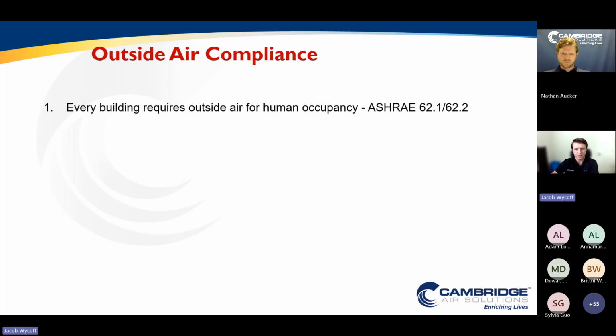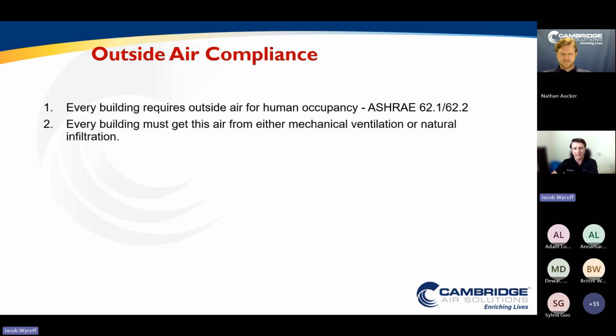So we know that every building is going to require some level of outside air for human occupancy. We know that from ASHRAE 62.1 building codes. Every building is going to have to get that air either through mechanical ventilation in most places with modern codes, or from natural infiltration. So even if the building does not require mechanical ventilation, it's going to have air infiltrating into the space somehow. And if you were to provide mechanical ventilation through 100% outside air, you're going to positively pressurize the space and reduce the natural infiltration that would have otherwise been occurring.